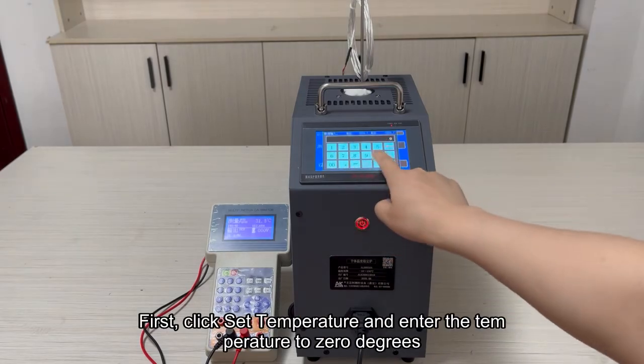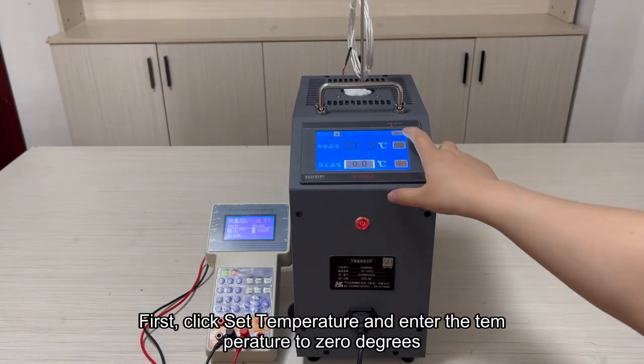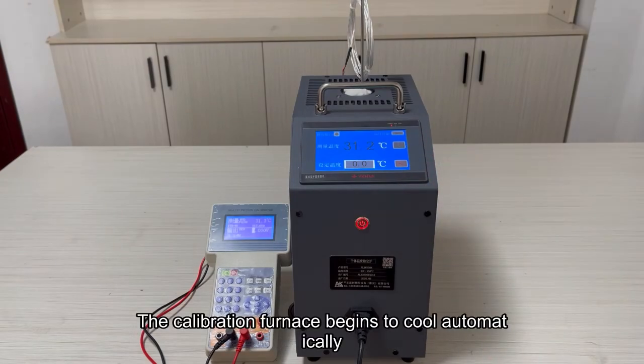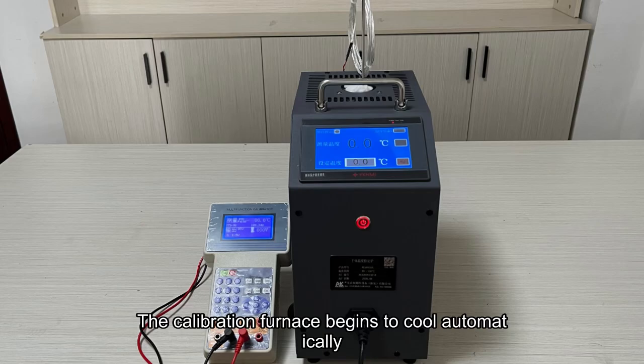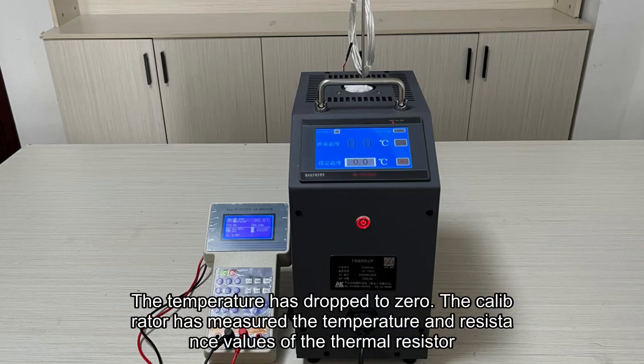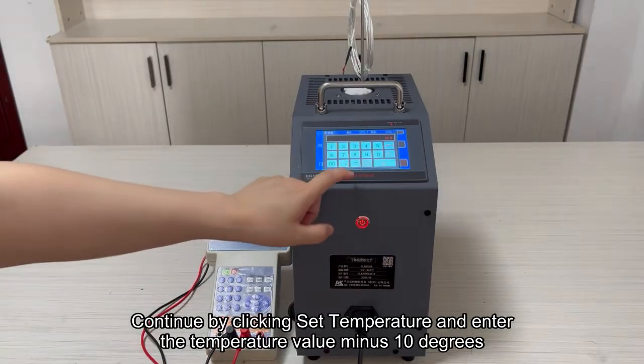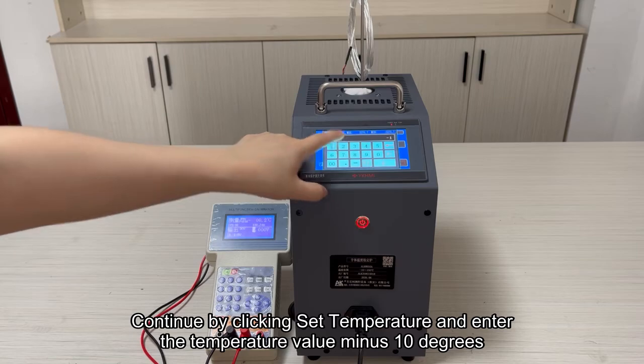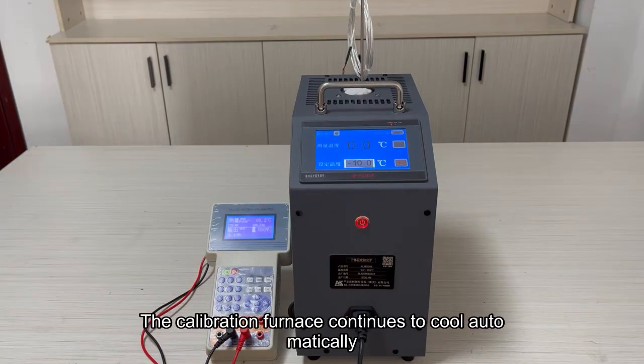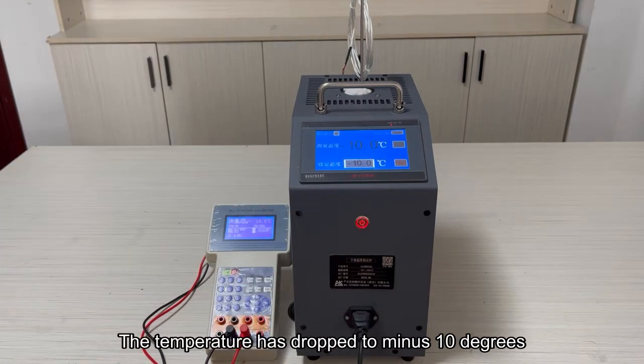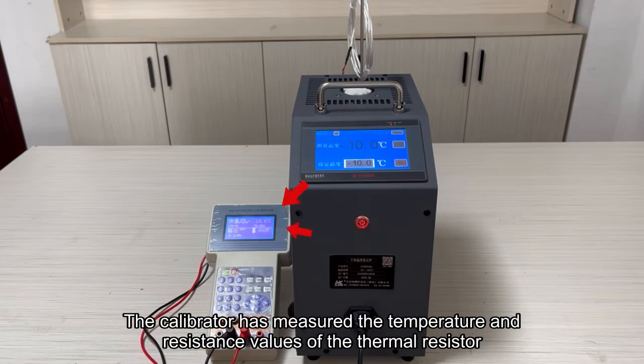First, click Set Temperature and enter the temperature to 0 degrees. Then click the Start button. The calibration furnace begins to cool automatically. The temperature has dropped to 0. The calibrator has measured the temperature and resistance values of the thermal resistor. Continue by clicking Set Temperature and enter the temperature value -10 degrees. The calibration furnace continues to cool automatically. The temperature has dropped to -10 degrees. The calibrator has measured the temperature and resistance values of the thermal resistor.